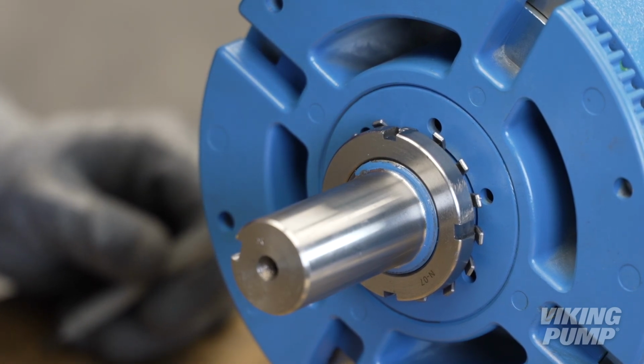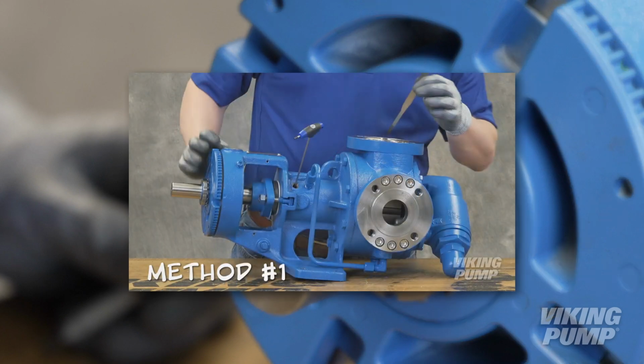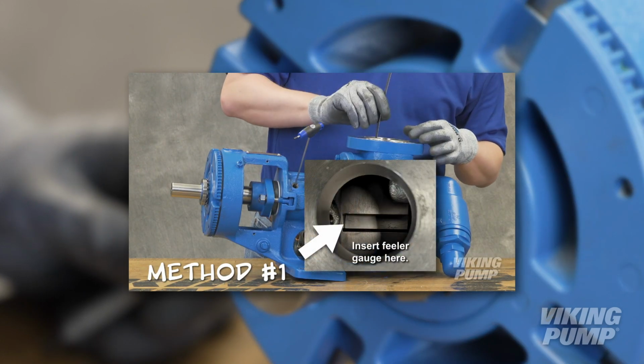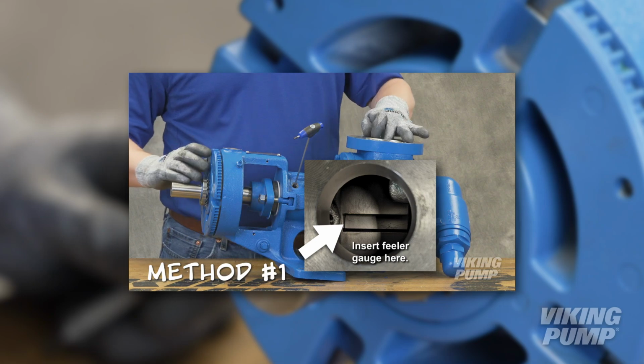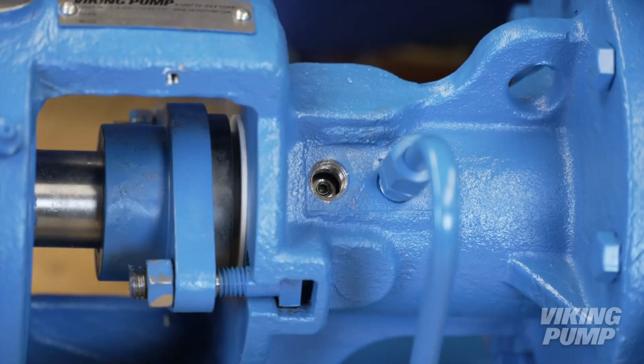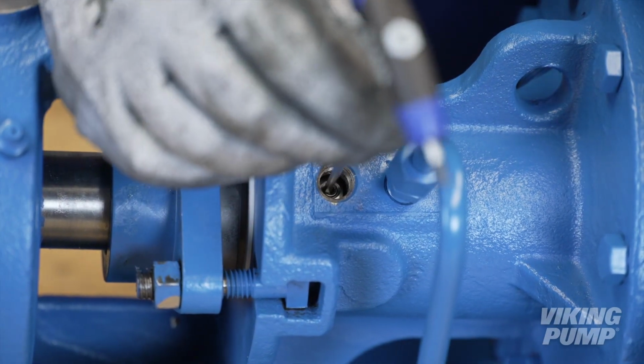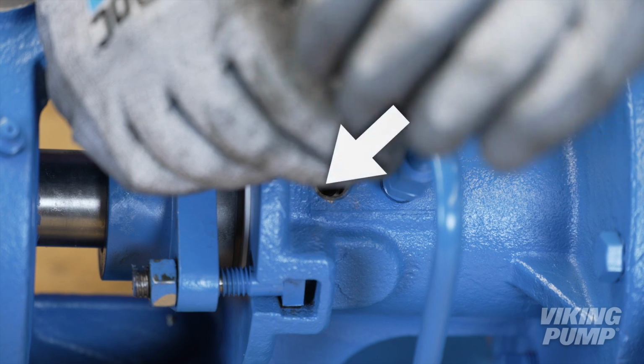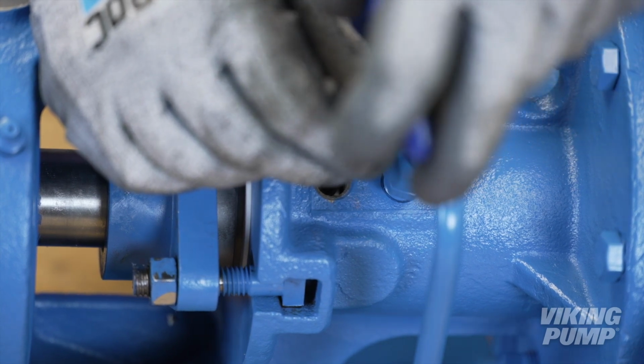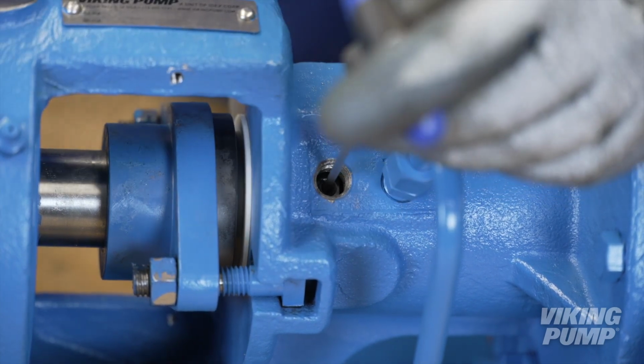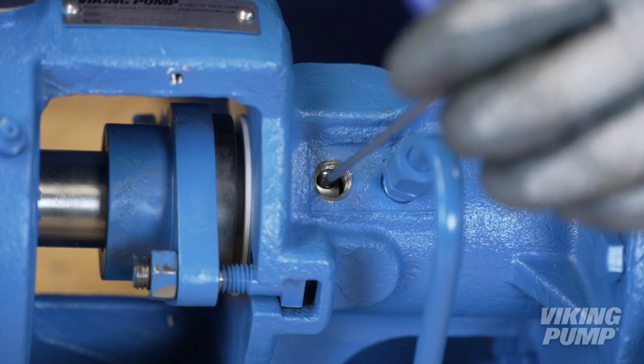Now set the end clearance. The end clearance setting can be found in the technical service manual. Please refer to our video, Setting End Clearance, for details on this procedure. You can now set the seal. Confirm that the seal set screws are aligned with the seal access hole. Tighten each set screw until it just contacts the shaft. Then fully tighten each set screw.